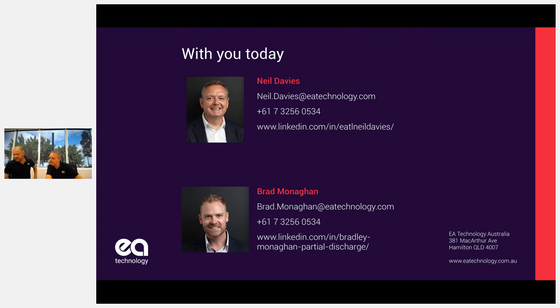Yeah, so Stanley's saying that with our PD testing program on 11 kV cable terminations, we've been successful in finding quite a few cases that would have catastrophically failed if left unattended. Just sharing the success story. Yeah, so that's what it's all about. Excellent. That's good. Very good. We had a good one.